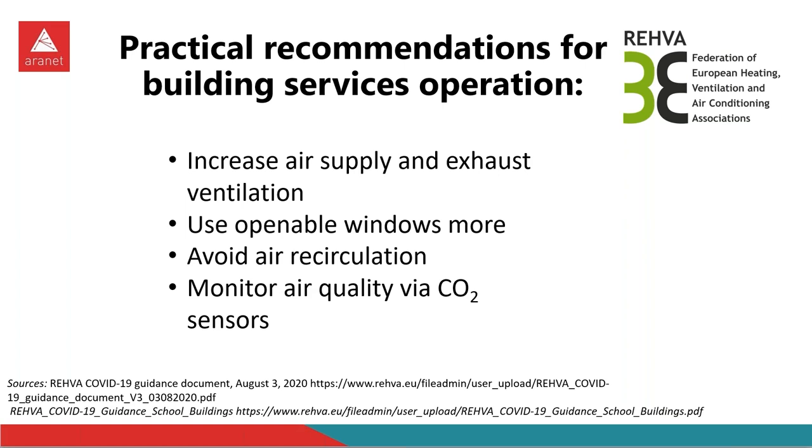With this, you can't have too much ventilation. A very important part here is really to avoid air recirculation. So what does that mean? Typically, the best way for buildings to be ventilated is to actually have all the time fresh air from outside, and the air should always be changing.